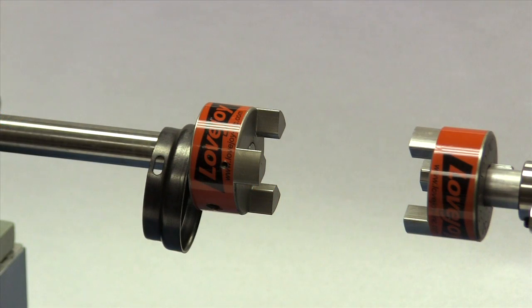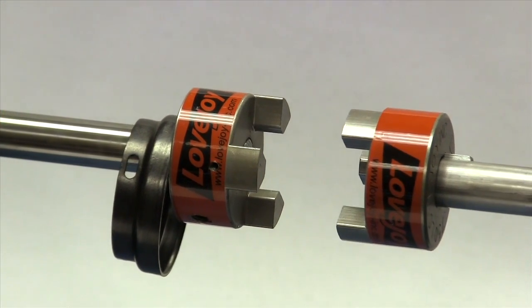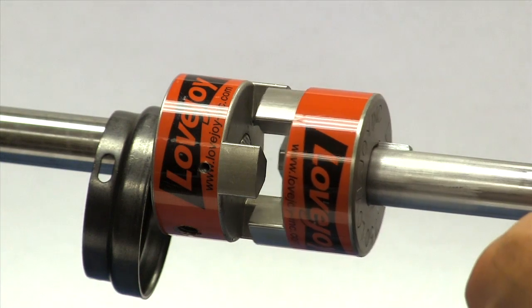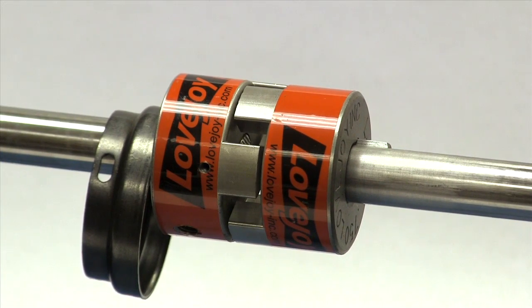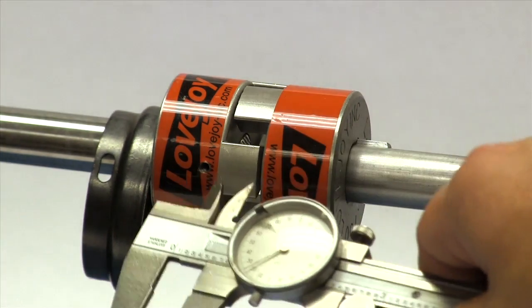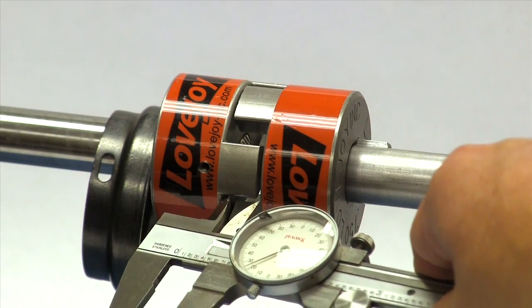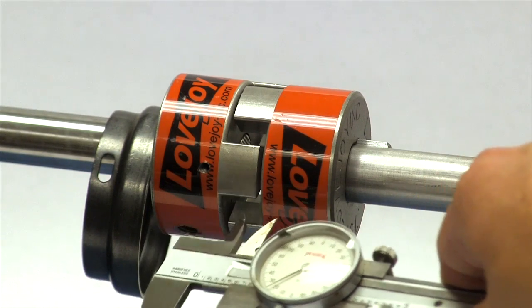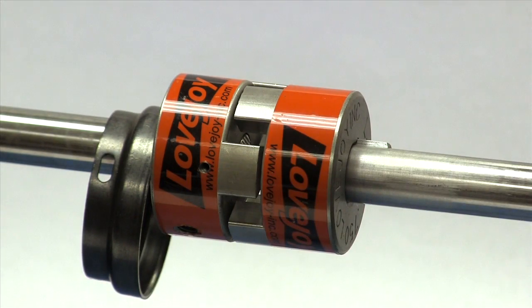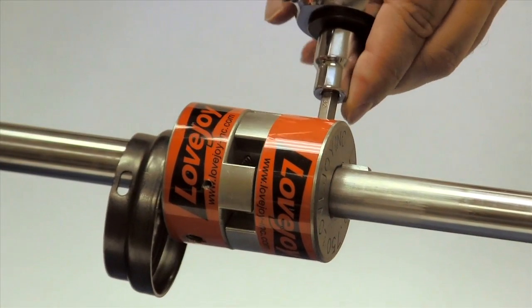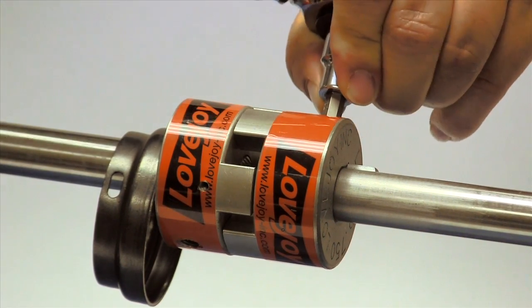Now we will carefully move the equipment into place bringing the hubs together until the gap between the hub faces matches the G or gap dimension in the installation guide. This dimension should match the installation document within plus or minus one sixty-fourth of an inch. Tighten the set screw in the second hub to the specified torque value.